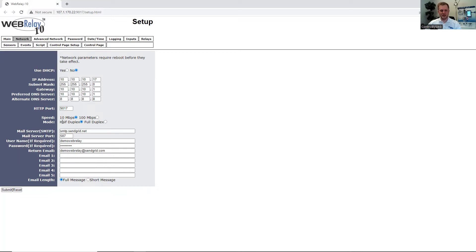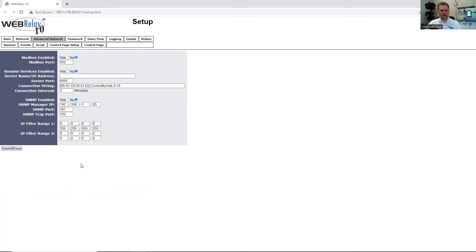Since the WebRelay 10 Plus supports email notifications, we can configure our email server or SNMP server settings here, and it supports up to five email addresses. There are also different length types for the email: full, which will display all of the IOs, or short, which will only display the IO that was triggered. Under the Advanced Network tab, we can enable Modbus, remote services, SNMP management, or an IP filter range.